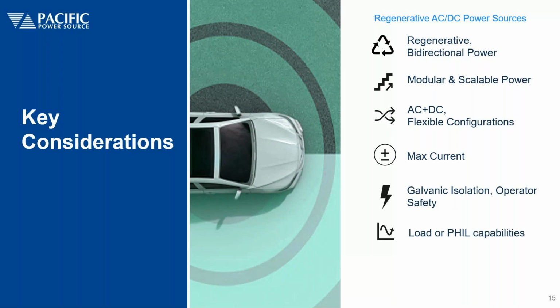Another thing to look at: are there additional capabilities and features available on the grid simulator you're contemplating? For example, a lot of regenerative grid simulators may have a load capability or load option, which can be beneficial for other testing you may want to do, as you can use the same product for that. And do you need power hardware in the loop simulation? So does the grid simulator have a PHIL or an HIL interface capability or option? Those can be important if you plan to do those kinds of real-time simulations as well.